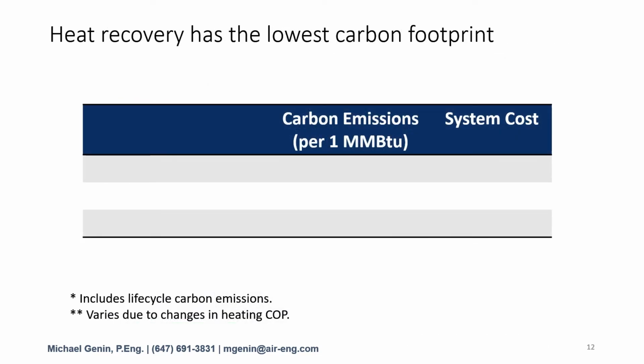When most people think of reducing greenhouse gas emissions, they might think of solar PV, wind, or some other green technology that's used or added to the building to generate new energy. But as it turns out, the most green thing you can do is to recover the heat energy you already have. Efficient condensing gas boilers, for example, here's how the numbers turn out. The system costs $30,000 and it will produce about 55 kilograms of carbon emissions per 1 million BTUs of heat.